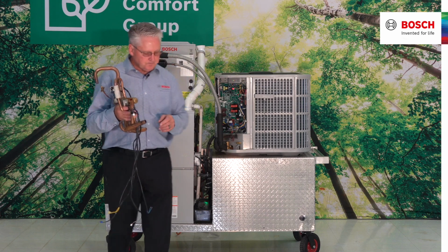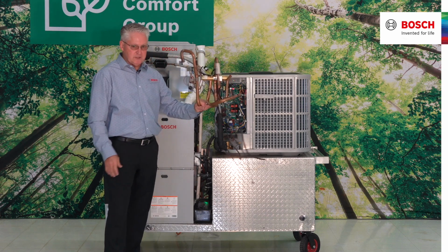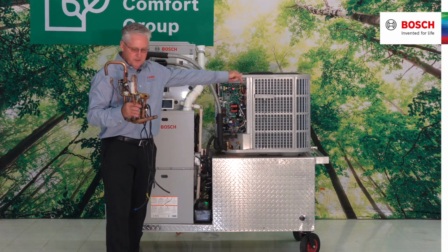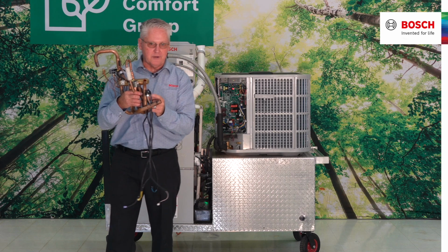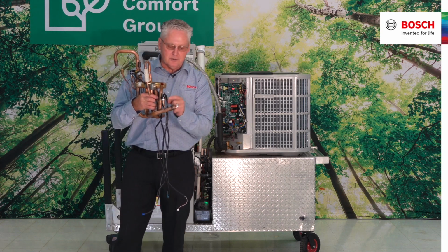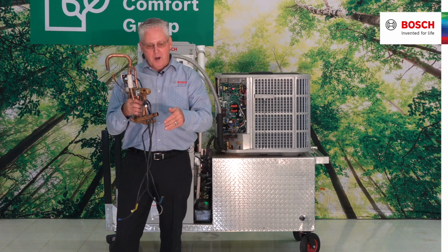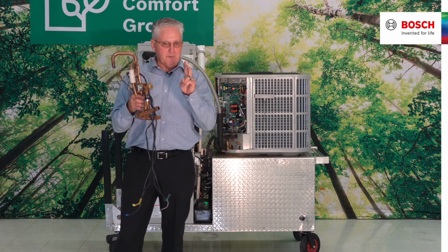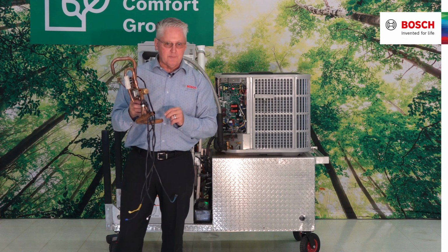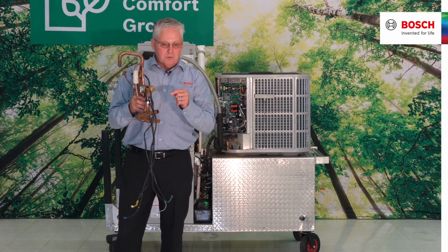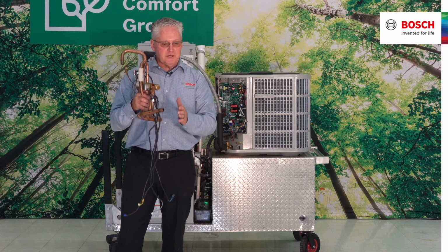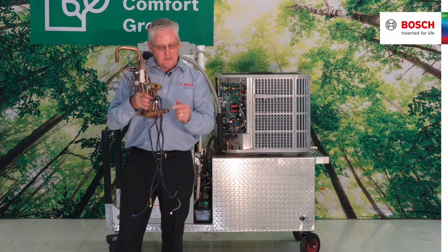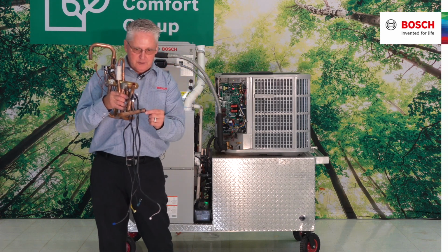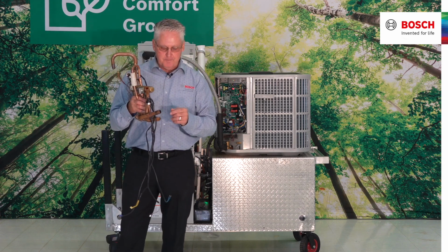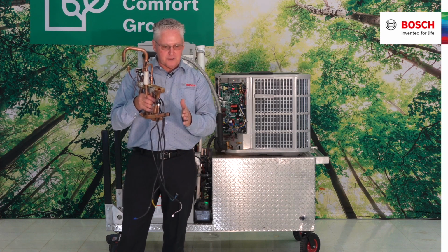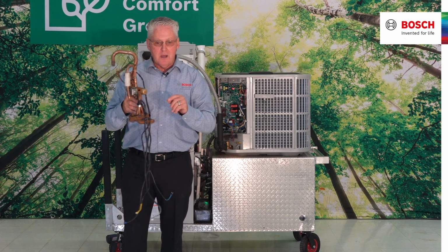It's very, very simple. In the refrigeration circuitry of the condensing unit, I have a device called a pressure transducer. That pressure transducer comes from Bosch out of the box to the contractor with 2 numbers as default — 108 for wintertime, 146 for summertime. Those two numbers are logically looking at a refrigerant pressure, which we can correlate to temperature, to modulate and keep our compressor steady.